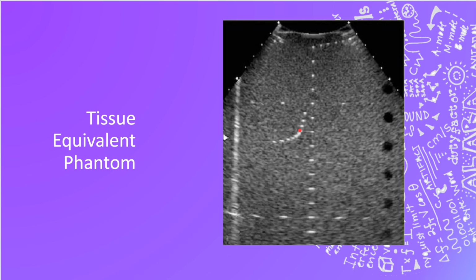When we scan from the top as well, we can also check our lateral resolution. Remember that side to side stuff. So now we're looking at 1, 2, 3, 4 distinct dots, but the number 5 and 6 start to blend together. So our tissue phantom shows us on the map that these two pins are way too close to be displayed as independent pins, even though they truly are. That gives us an idea of how the axial and the lateral resolution are affected by the transducer selection or by the focal point, wherever that is placed.